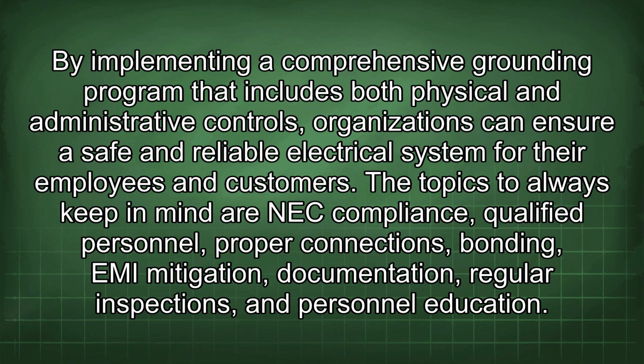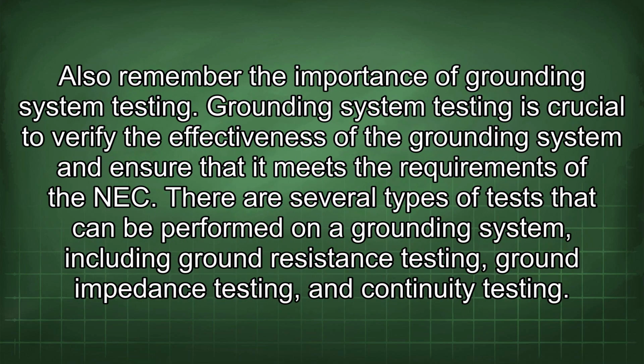The topics to always keep in mind are NEC compliance, qualified personnel, proper connections, bonding, EMI mitigation, documentation, regular inspections, and personnel education. Also remember the importance of grounding system testing. Grounding system testing is crucial to verify the effectiveness of the grounding system and ensure that it meets the requirements of the NEC. There are several types of tests that can be performed on a grounding system, including ground resistance testing, ground impedance testing, and continuity testing.